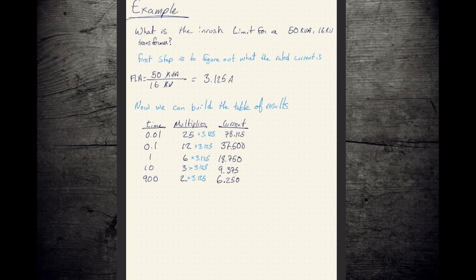Now, be careful with your units. It's fine to divide kVA by kV, but you wouldn't want to divide kVA by V. You'd be off by a factor of 1,000. You'd get kind of a strange number. I like doing it the unit analysis way. Make sure that things don't go off the rails. I may ask you this question with mixed units, so please pay attention. Either make sure that everything finds its way into base units, so 50,000 VA over 16,000 volts, or make sure everything is in kilounits, 50 kVA over 16 kV. Doesn't matter, but you have to be consistent or your math will blow up.